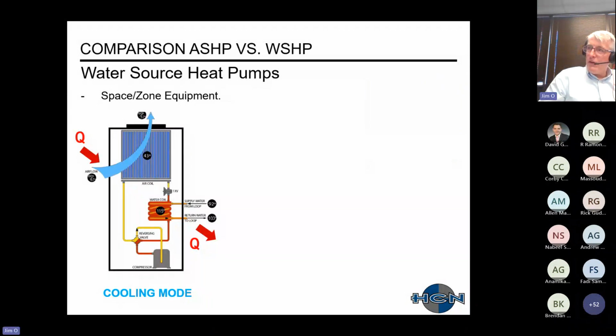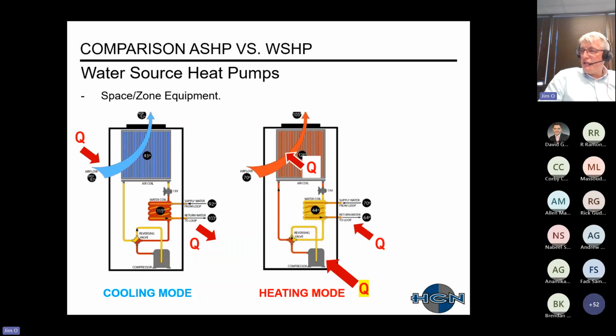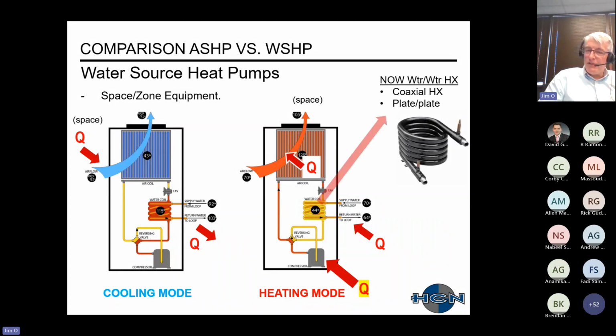Once again, a cutaway view of a water source heat pump. So in cooling mode, you're essentially running your air across your evaporator. You're dumping that energy into the refrigeration system. You're then expelling it in the center there with a source of water from a loop. The opposite happens in heating. You're taking the heat from the source. You also want to highlight that you're adding the heat from the compressor, and you're discharging it into the space. What ends up happening is that the heat exchanger changes to a water-to-water heat exchanger, which could be a coaxial heat exchanger shown there, refrigerant in a tube within the other, as well as a plate-to-plate on larger sizes.